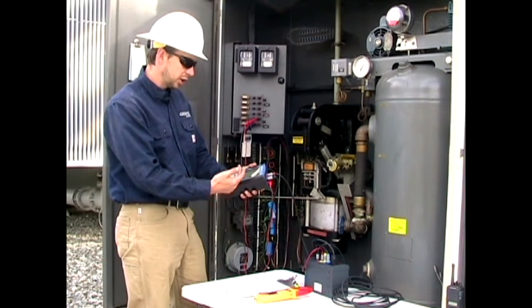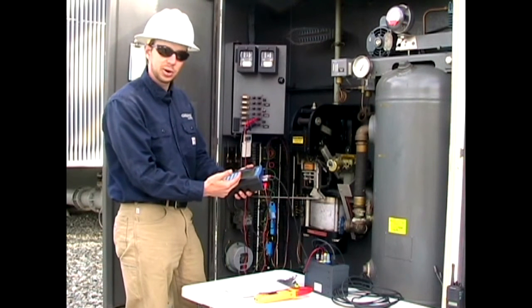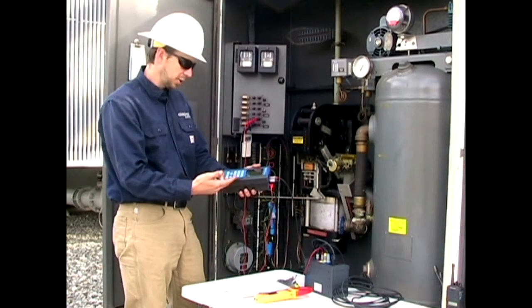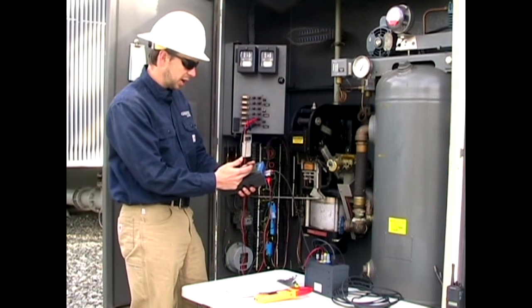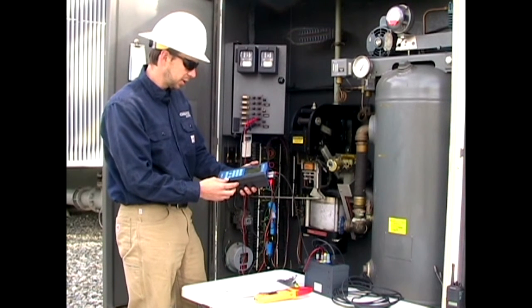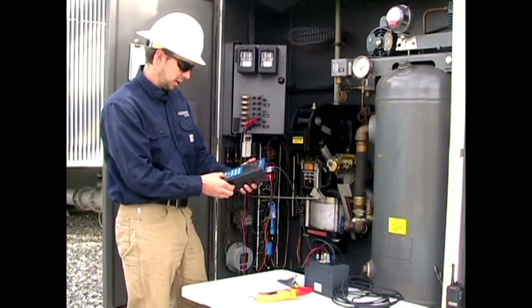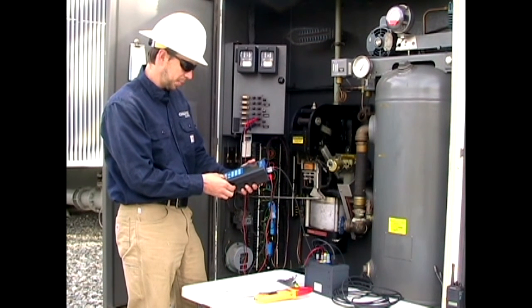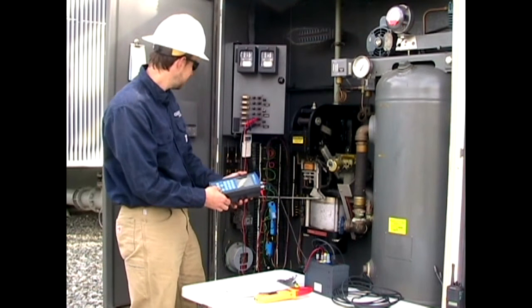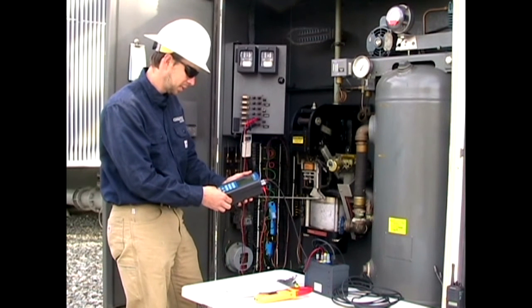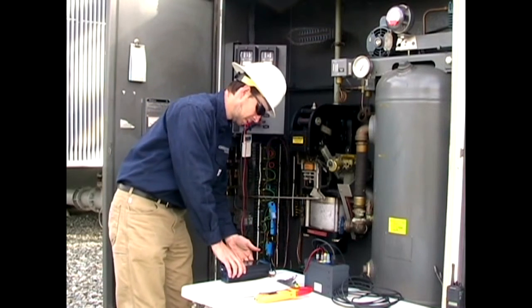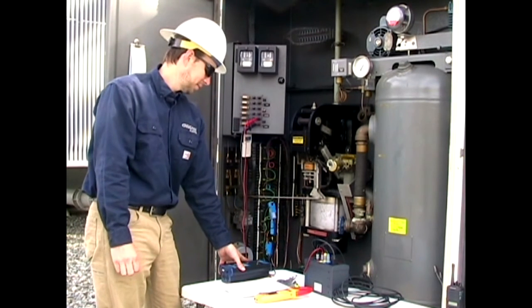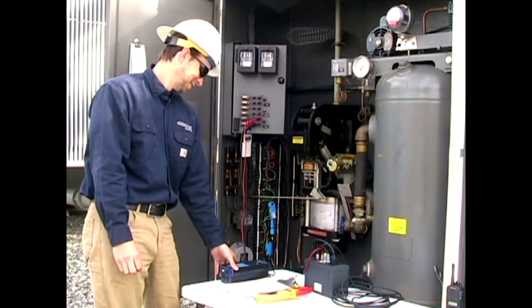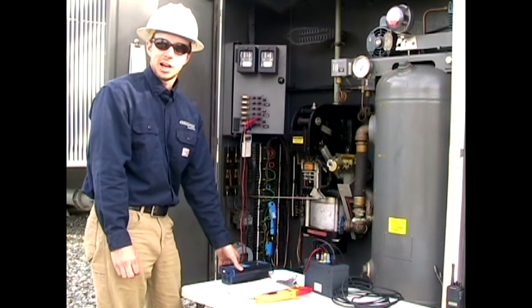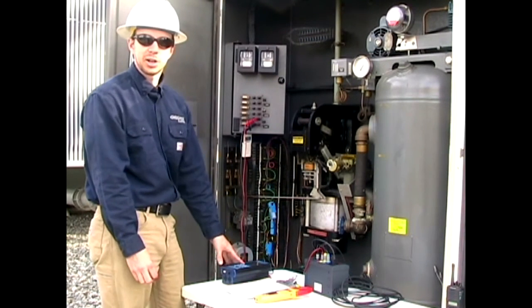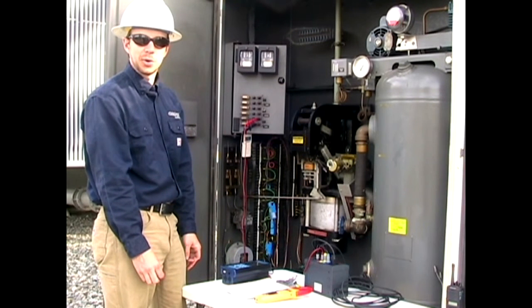You have to enter the information: your substation, your breaker type, your breaker ID. I've entered this in. You enter it like you would text on a cell phone. And this is International Sub. This is a Westinghouse AA10 breaker. Breaker's number 1616. And we're going to perform a trip. So everything's connected, turned on, hit OK. Now our profile is armed, and we'll get the clear contact dispatch, have them trip it open and report it.